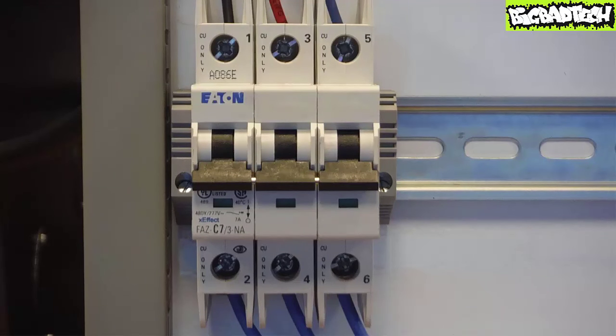Despite the asymmetric nature of the fault in this case, a short between L1 and L2, note how all three poles simultaneously open. Again the simultaneous opening and closing of all three contacts is yet another advantage circuit breakers offer over three uncoordinated fuses.